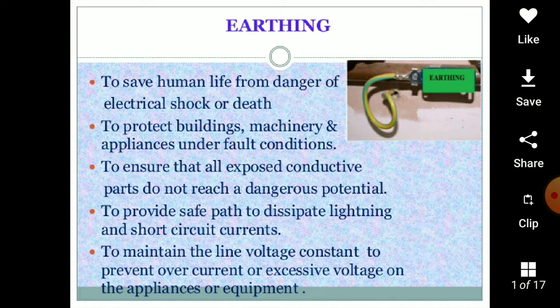This earthing is very much necessary in all domestic, commercial and industrial installations where the operator has to be protected against electrical shocks, or we can say death also. And we have to provide this earthing to protect the buildings, equipment, machineries and appliances under any kind of fault such as lightning fault, and also to serve as a return wire in traction work. Most of the electrical applications in traction work use the earthing wire as a return wire also.